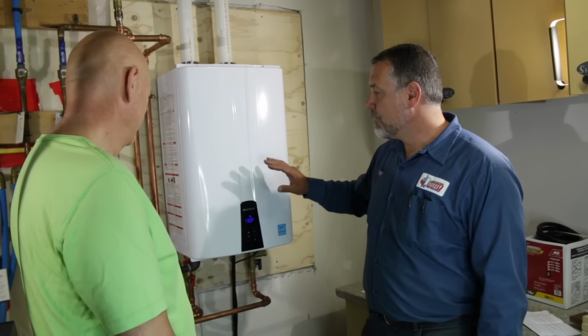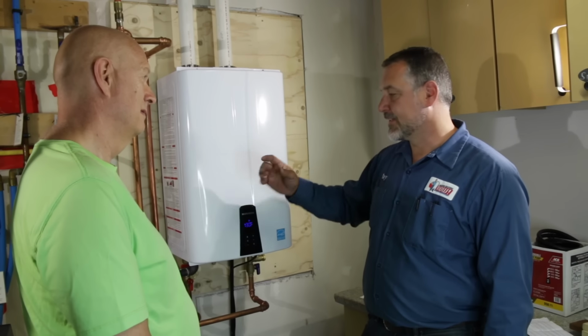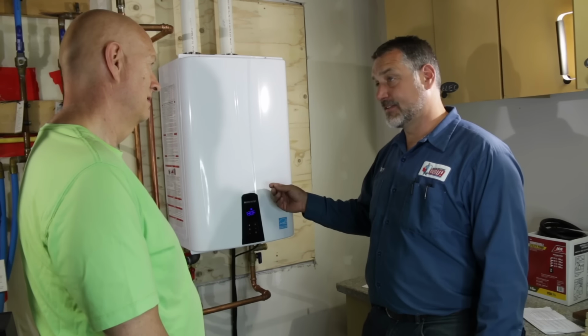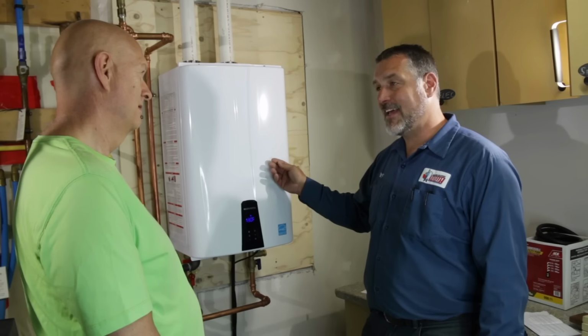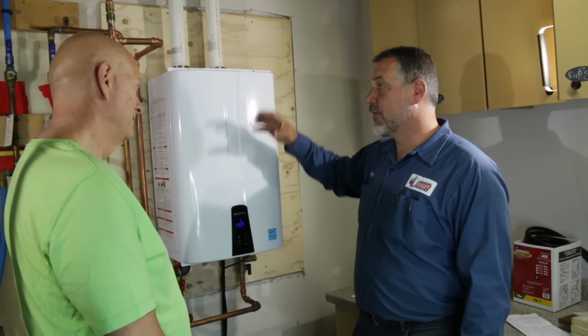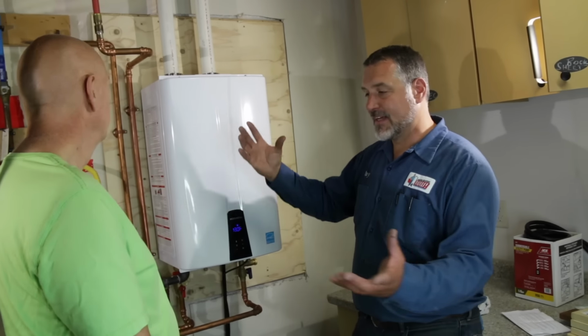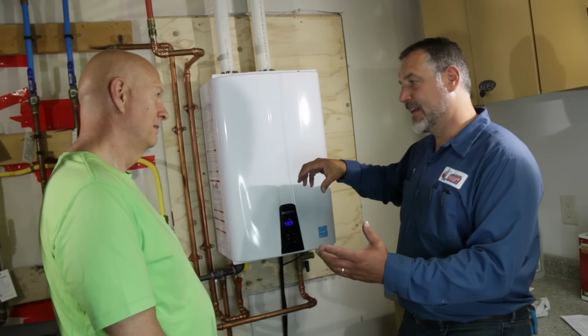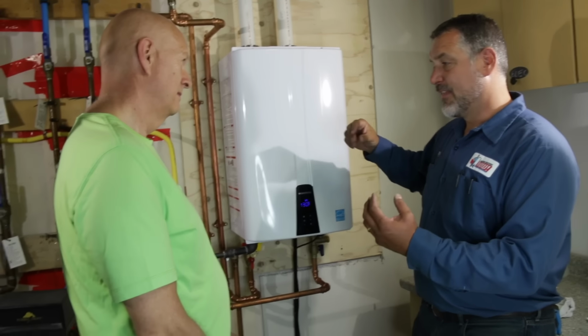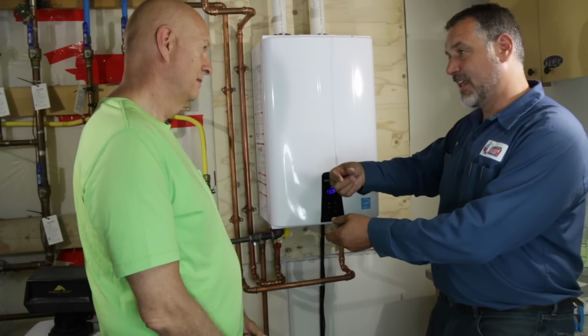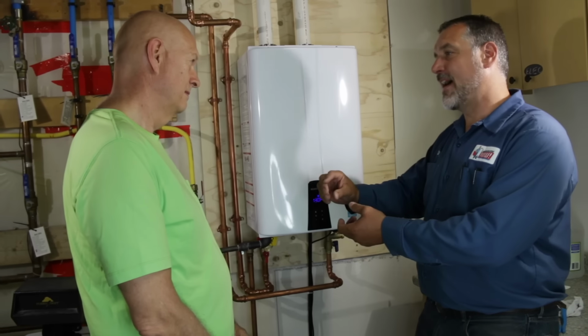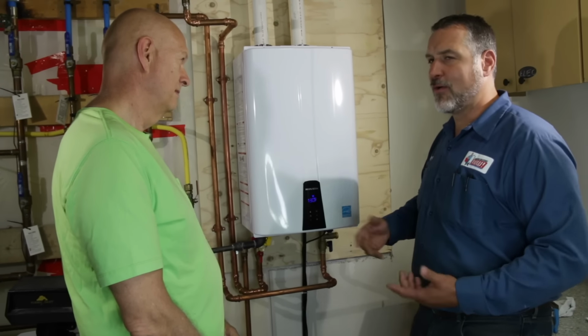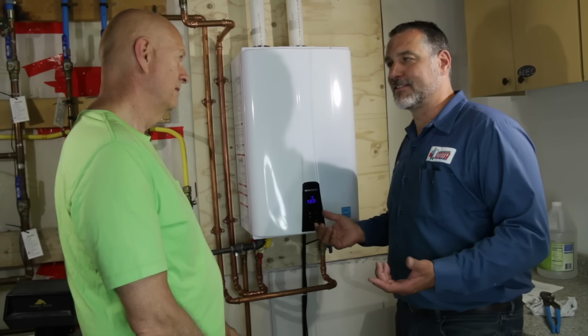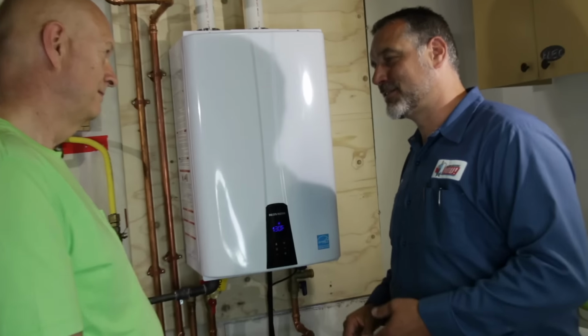Right. So now, when you turn a hot water faucet on, water comes through the heater, it hits a sensor, tells it I need heat, turns the gas valve and the inducer on. They mix the air and gas, pump it into the firebox. The firebox heats up the steel plates, and then the water that passes through can begin getting heated. That whole process takes about 10 seconds each time you turn a hot water faucet on.